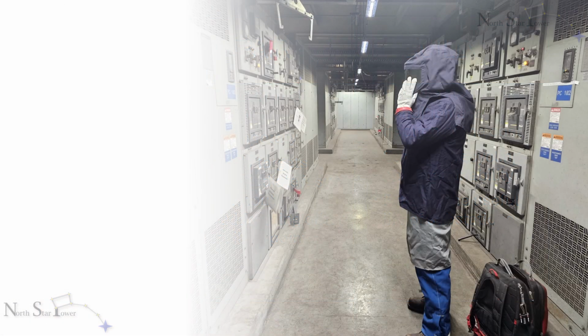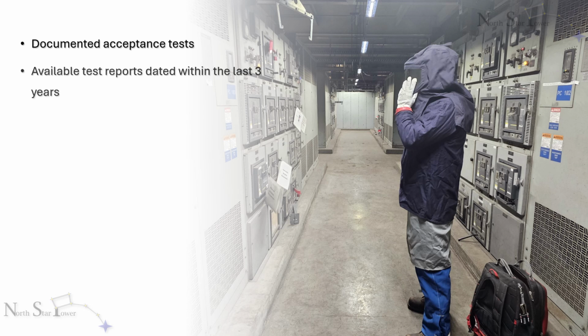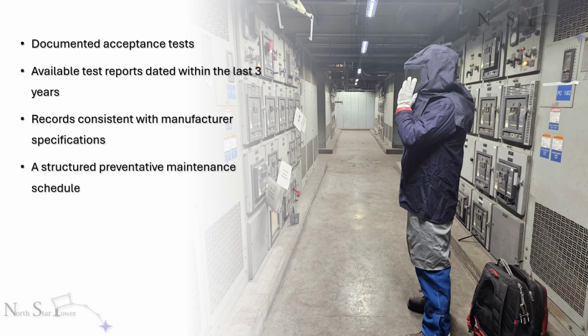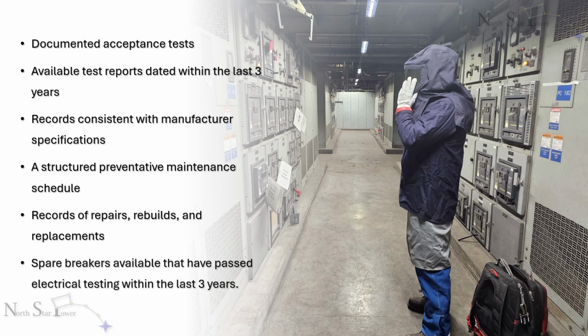In the end, we can take any mystery out of electrical safety. When auditing an electrical system, we can see proactive attention to safety in documentation, testing, and planned maintenance schedules. A compliant electrical system should have documented acceptance tests, available test reports dated within the last 3 years, records consistent with manufacturer's specifications, a structured preventative maintenance schedule, records of repairs, rebuilds, and replacements, and spare breakers available that have passed electrical testing within the last 3 years.